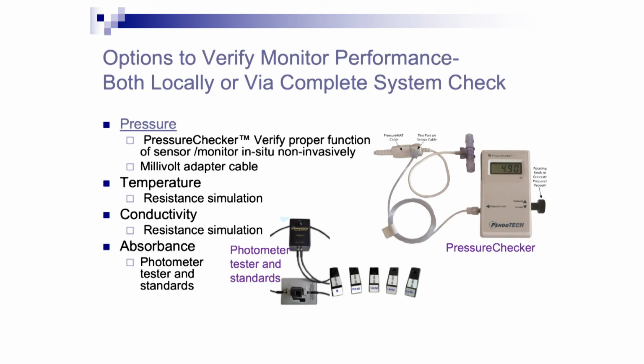So single-use sensors really create a paradigm shift for metrology groups, which are used to traditional sensors. But with single-use sensors, you really, in most cases, are breaking it into 2 separate elements, a monitor and a sensor. So metrology groups feel the need to maintain their monitors even if there's no sensor connected over time. So we have tools, and any manufacturer should have tools to be able to test the monitor periodically to make sure it's still doing the proper measurement.